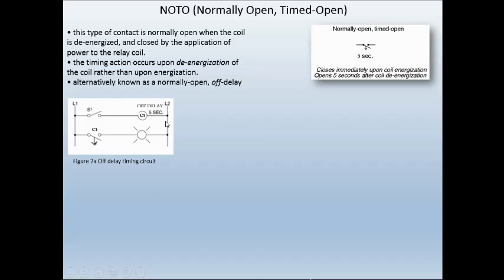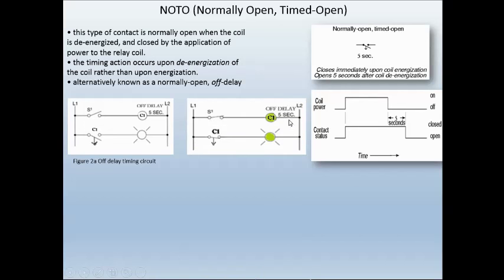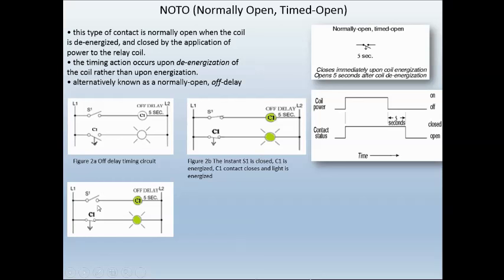Let's look at its functionality. In this drawing, we have our switch and here's our C1 coil. This time it is an off delay — very important that we know that, and it needs to be noted so we know how this coil and contact will react. I want you to look at the arrow pointing down, which tells me that when the timing operation is completed it will come down. We have the coil de-energized at first — coil power is off, contact status is off. When we close the switch and energize the coil, at that very same time, the contact for C1 closes.